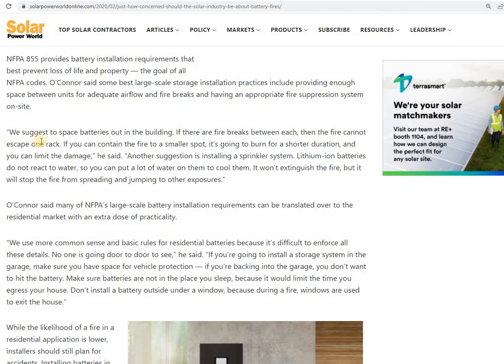They also suggest spacing batteries out in the building. If there are fire breaks between each, the fire cannot spread or escape one rack. If you can contain the fire to a smaller spot, it will burn for a shorter duration and you can limit the damage. Another suggestion is installing a sprinkler system. Lithium-ion batteries do not react to water, so you can put a lot of water on them to cool them. It won't extinguish the fire, but it will stop it from spreading and jumping to other exposures.